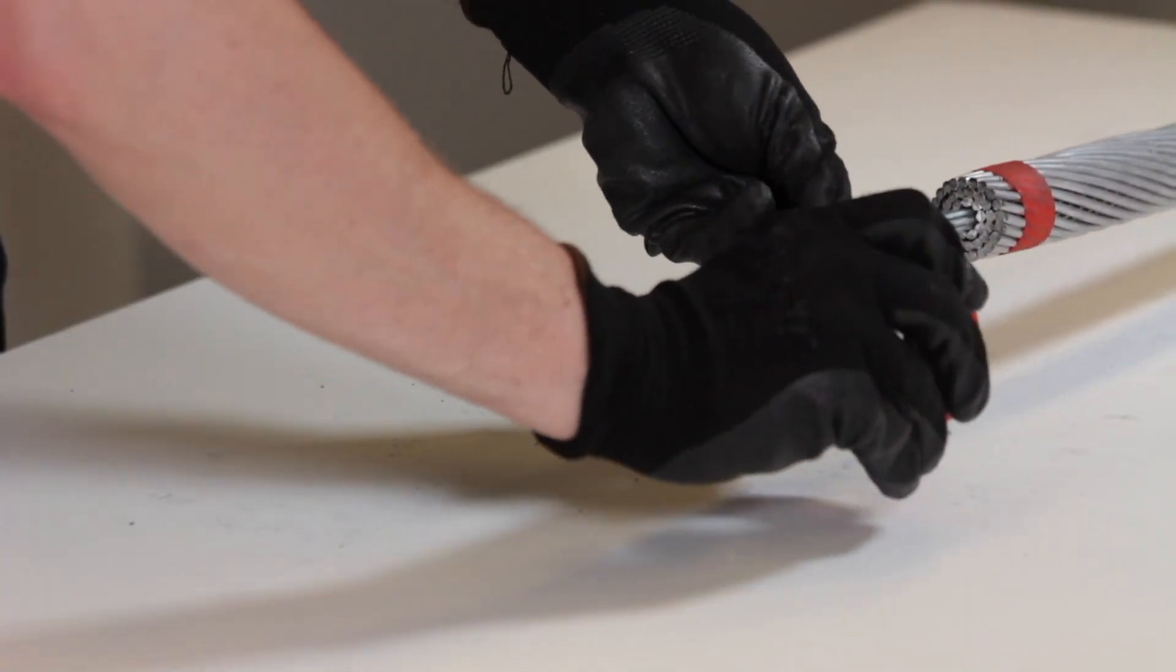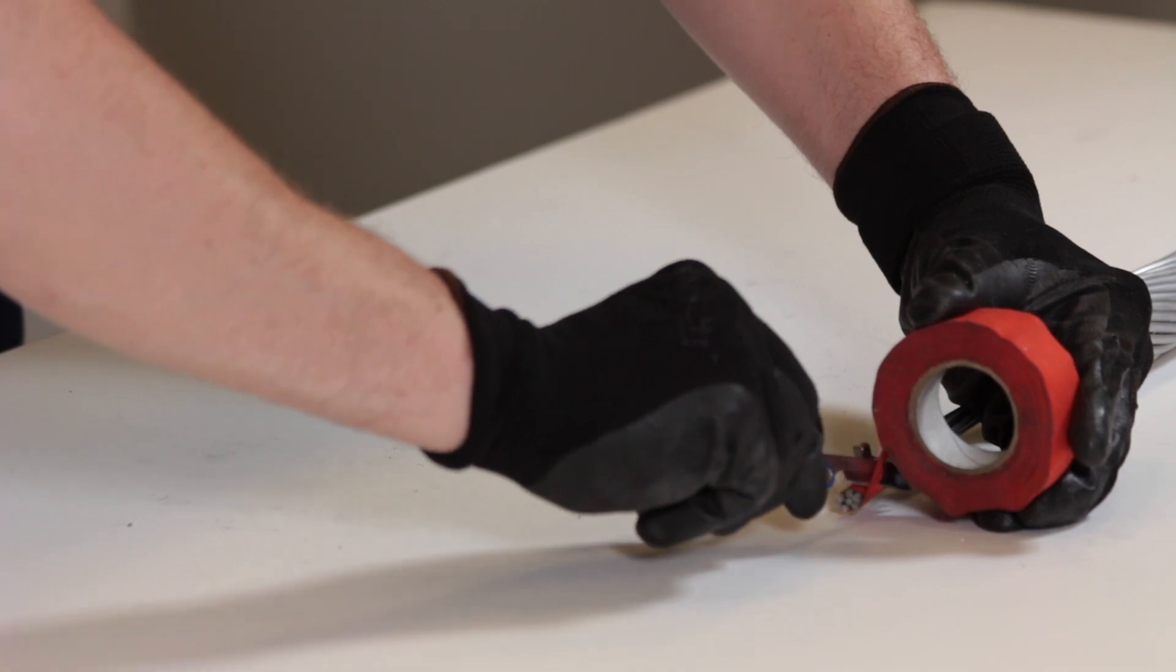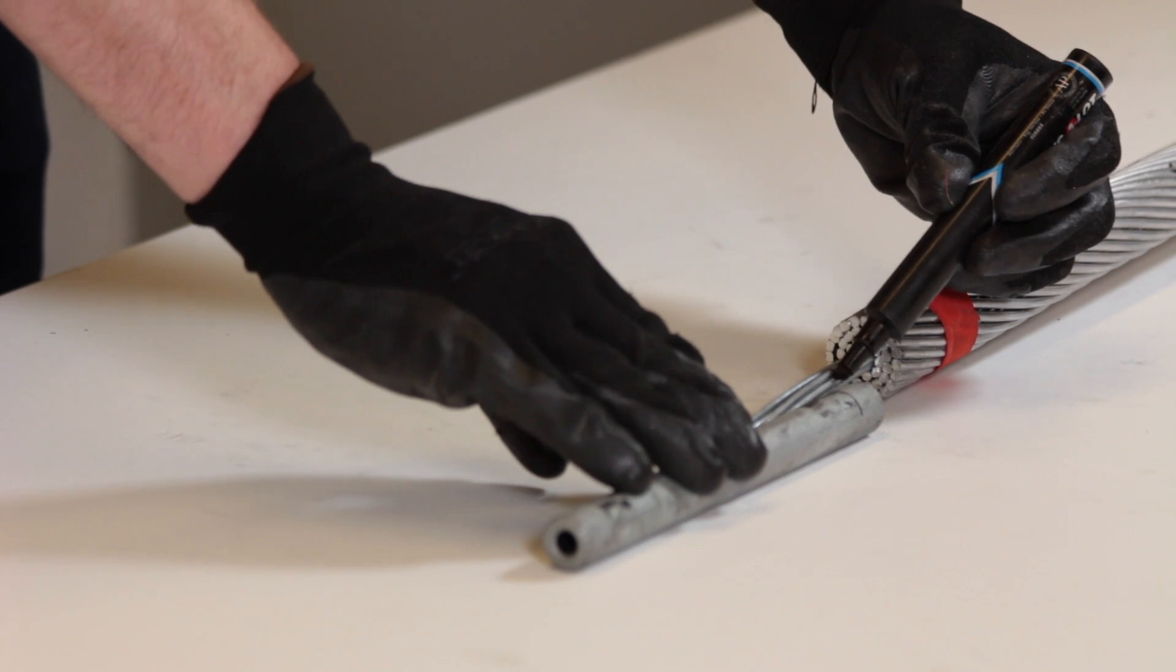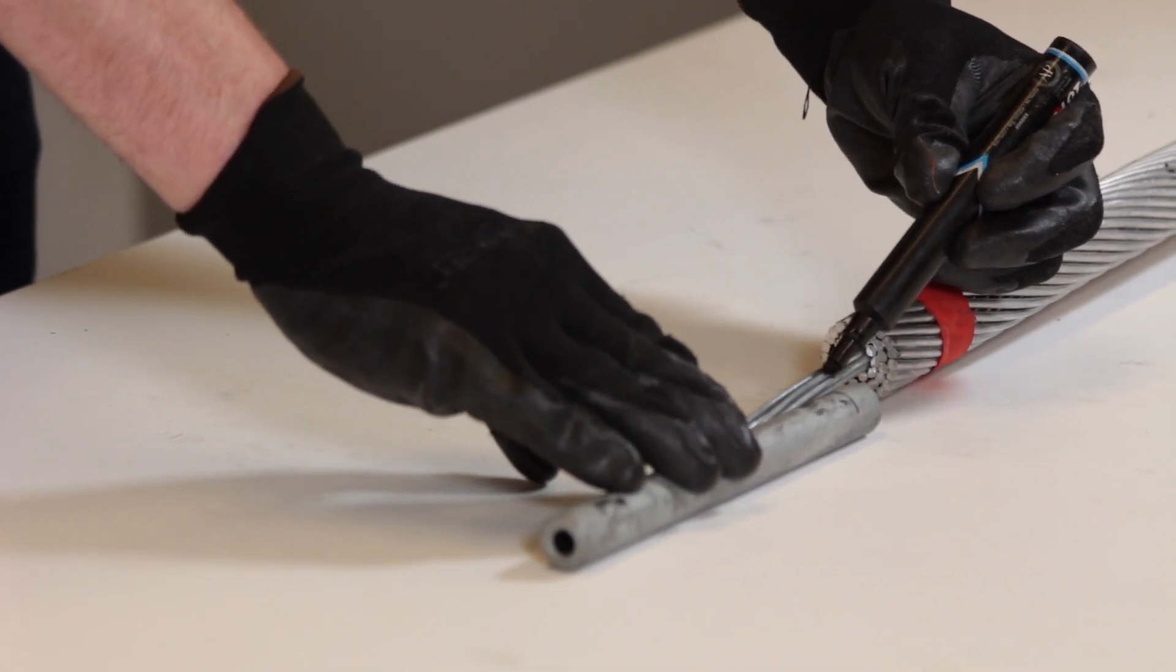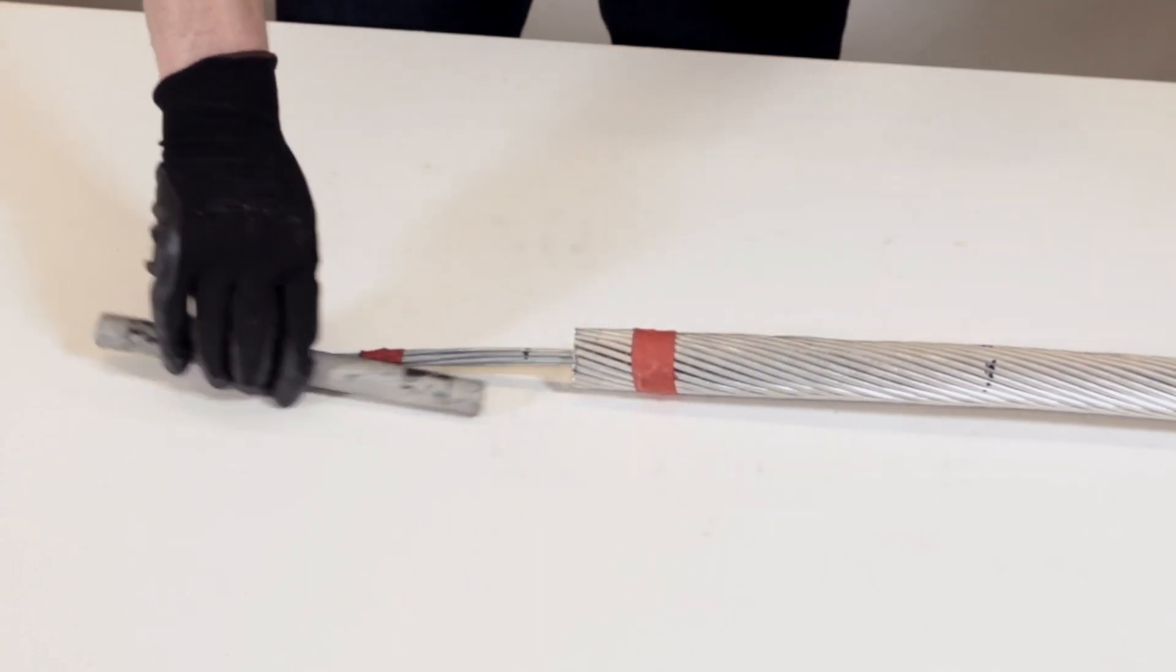Secure the conductor core strands with tape. A hose clamp can also be used to help hold the strands in place while tape is applied. Mark the depth of the steel tube to the center knurl on the conductor core strands. Repeat all preparation and measurement steps for the other conductor to be spliced.